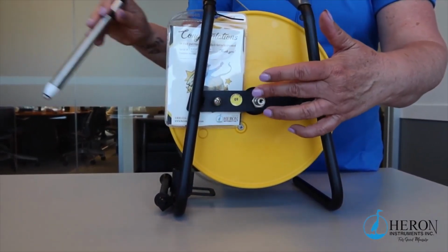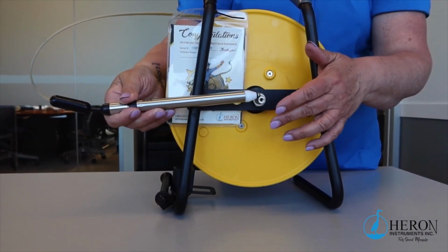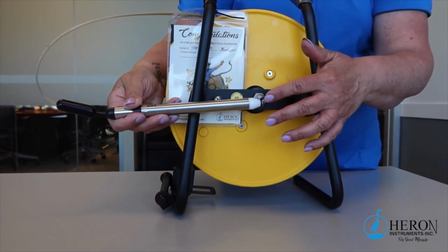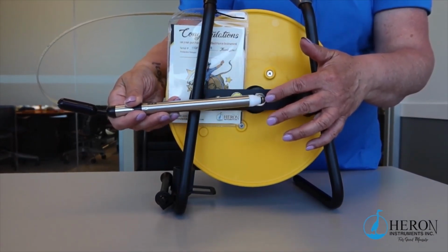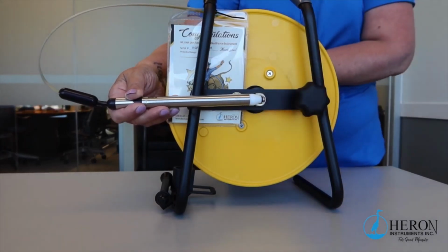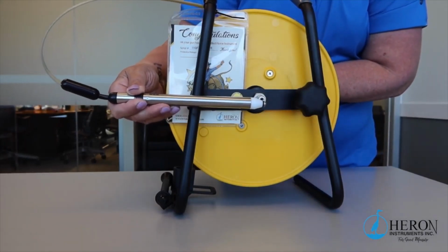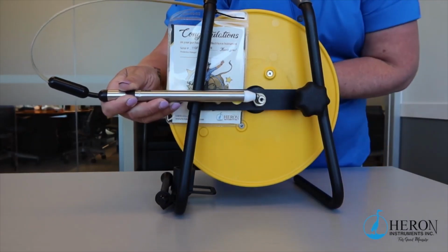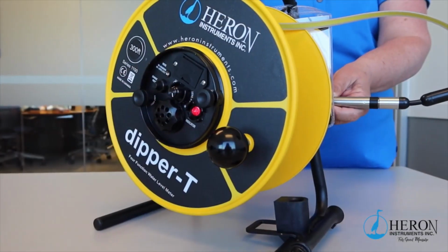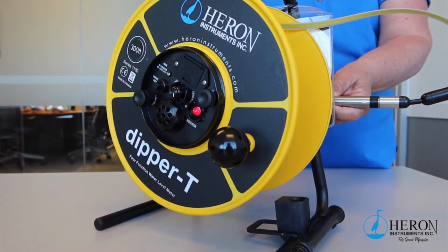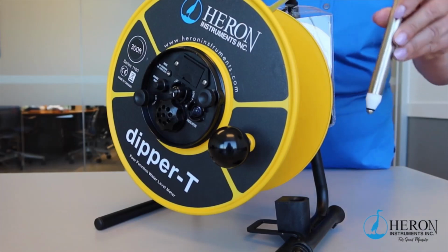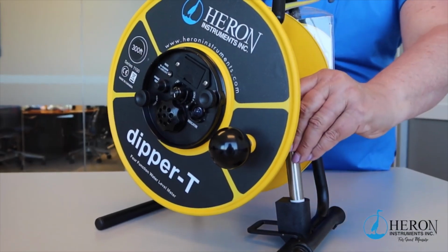Before you go out in the field, we suggest testing the unit to make sure everything is working properly, including battery power level. Hold the probe tip to the center shaft and the body to the screw at the same time. This will complete the circuit, sending the signal from the probe up the tape to the electronic panel. The buzzer will sound and the LED lights will turn on. We suggest you always carry an extra 9-volt battery in your backpack just in case.